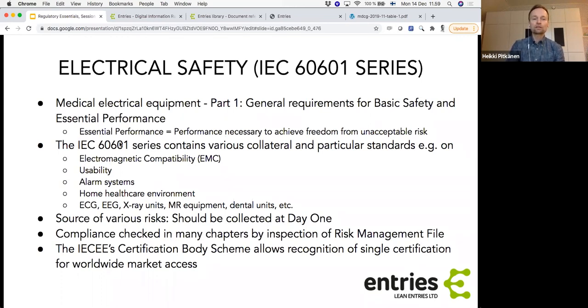Then you need to understand that the 601 standard contains various collateral standards and also particular standards. Collaterals would be on the horizontal level, like the EMC, that needs to be taken into account for all types of medical devices, and usability as well, alarms. And if it's a home healthcare environment, that would also be a collateral standard for any devices that are brought home. And then there are the vertical standards, which are the particulars, and they dive into specific technology, for example, the ECG, EEG, X-rays, MR, and such.